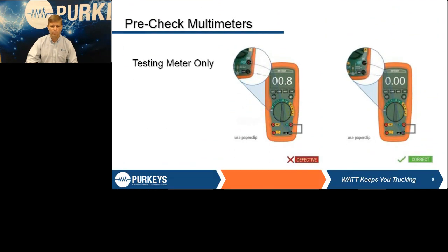First, take both your meter leads out. Just grab a paper clip or a short piece of wire and jumper across those two ports. You should get a zero reading, or very, very close to zero. On most meters, 0.1 is going to be in the range of being correct. But if you get very far off, that's going to impact all your readings on any resistance check you do. So you've got to make sure those leads are right.